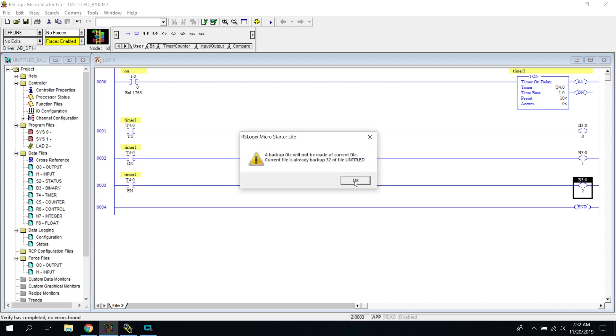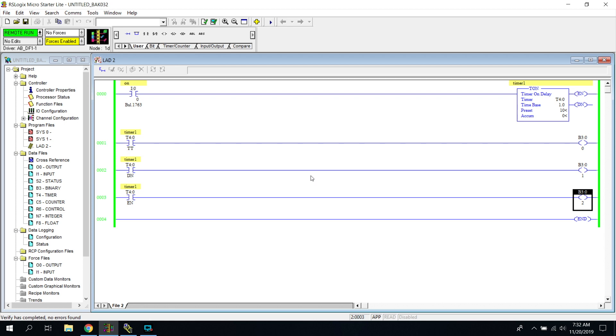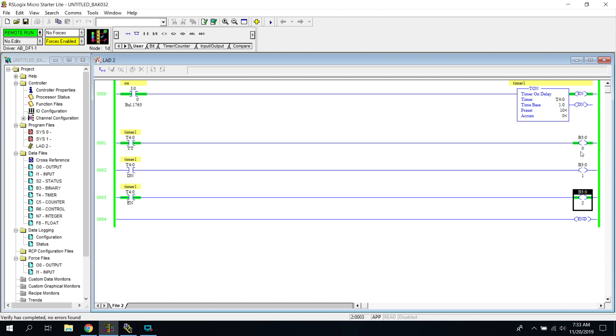I'm going to download this and go online. Now I'm going to press and hold my button — with a timer it always has to have a rung of true to keep it going; as soon as the rung of true is broken, the timer will reset. I press the button and you can see it's accruing time. The timer timing is on and will be on for 10 seconds. Once it hits 10, it turns off. Notice the timer done is now on because our timer is done. The enable just came on and stayed on the whole time. When I release the button it resets the timer. If I release at around 5 seconds, it resets — so anytime you want to reset a timer, you just need to break the path of true.